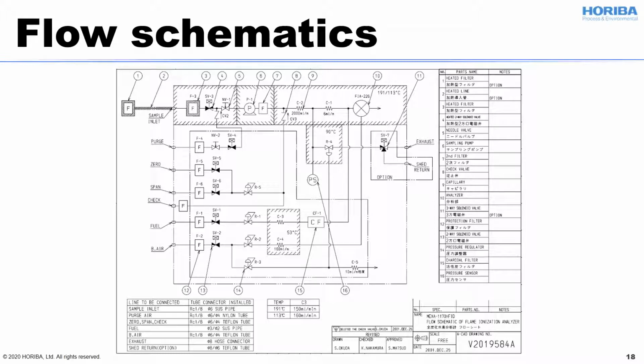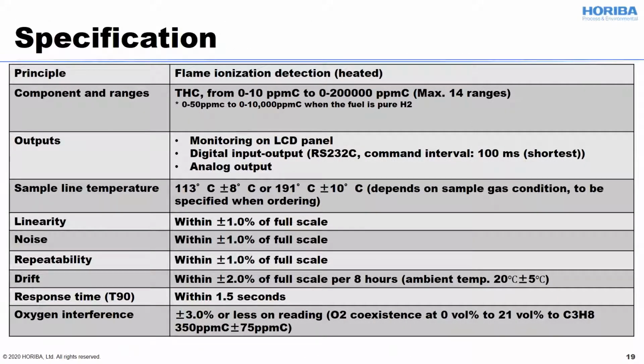The sample gas is pulled by a built-in sampling pump and the flow into the analyzer block is regulated. So you can see there is a purge line, zero gas line, span line, the fuel line, and a purified air line. Here are the specifications. The analysis method is heated flame ionization detection, and the range is as written right here, from 10 ppmC to 200,000 ppmC. But please note that when pure hydrogen is used for fuel, the range is narrowed down to 50 ppmC at the lowest and 10,000 ppmC at the highest. Still, you can set up 14 ranges in any case.